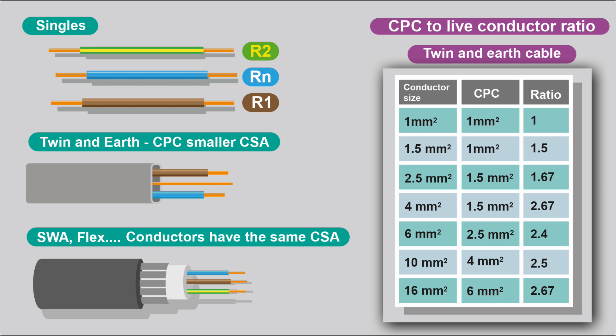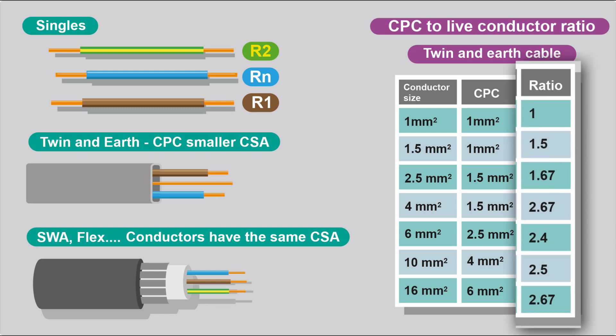10 has a 4mm CPC, and 16 has a 6mm CPC, sometimes it's 10. And as you can see, there's a ratio there, the cross-sectional area of the line conductor compared to the CPC.